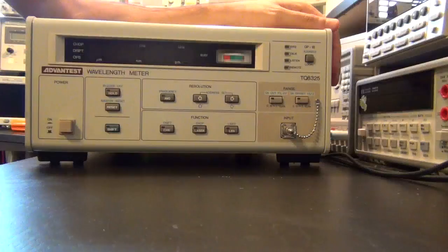It can measure the wavelength of any light source that you put into it, anywhere from 600 nanometers to about 1600 nanometers. So it covers just where red is, all the way into deep infrared. It's used for optical telecommunication. But I'm also going to show you some of the electronics that's inside, and then we're going to do a little experiment and measure a particular laser that is in the infrared region. We're going to put it in, do some measurements versus temperature. So let's take this apart, get started, and see what it looks like.